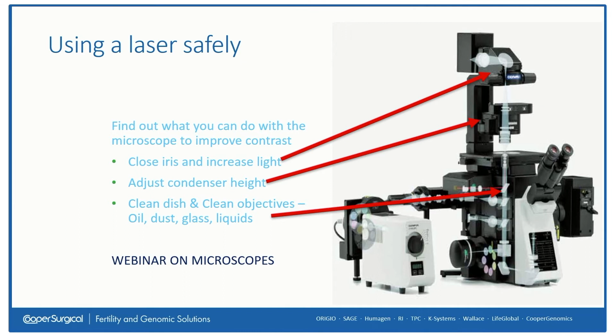Next, the height of the sample can also have an impact on the energy which can reach it. The laser objective lens is designed to focus the laser beam at a specific point, a fixed distance above the lens. It's known as the working distance, or WD. And this is where the embryo should be to get the most efficient transmission of laser energy, and it's basically at the bottom of the dish.